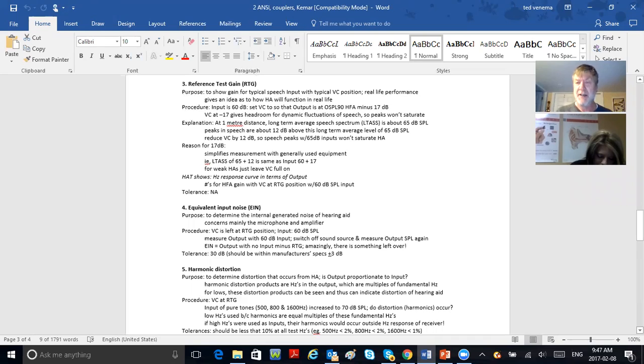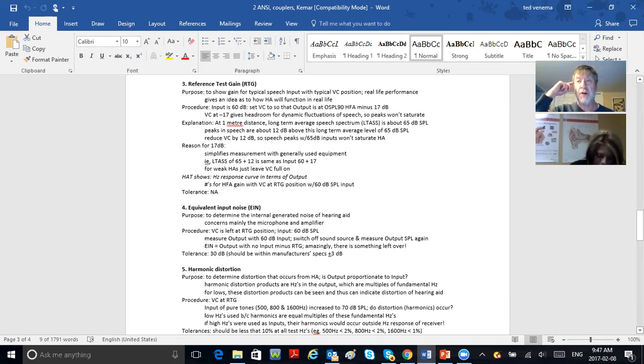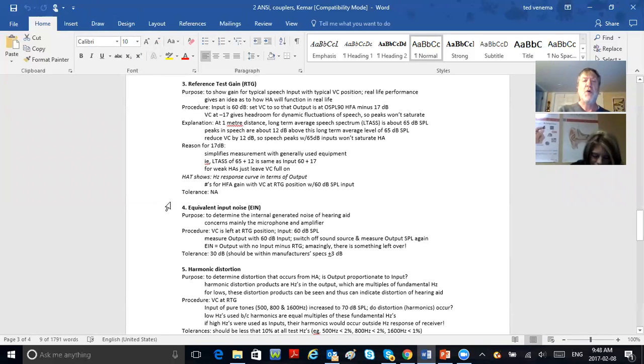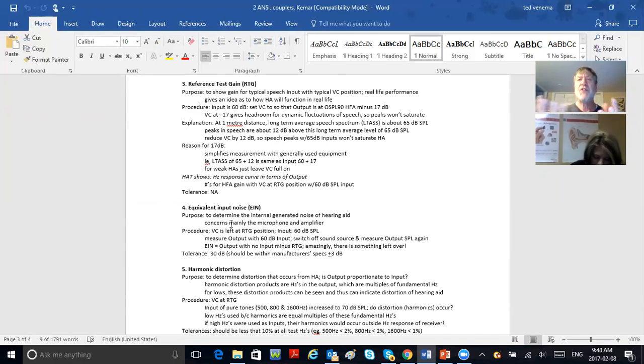The third test is called reference test gain. The input is still 60, but now you've got the volume reduced to a user volume—more like half or two-thirds—and reference test gain is meant to look at how the hearing aid is going to function in everyday life at a user setting with average inputs like speech. The fourth thing is equivalent input noise: you're looking at the internal noise produced by the hearing aid, from the microphone and amplifier.